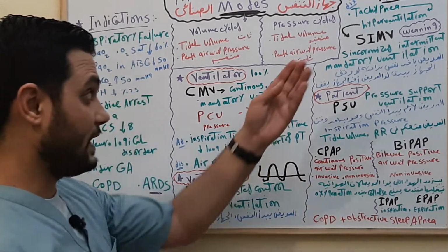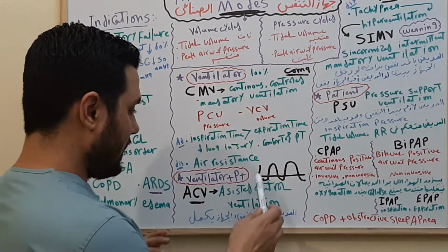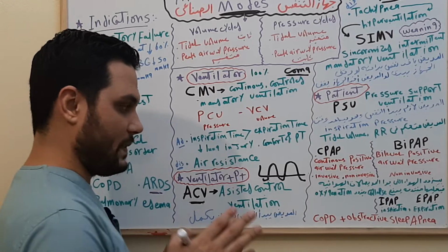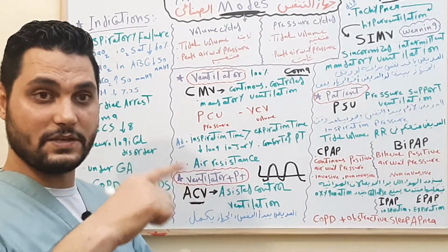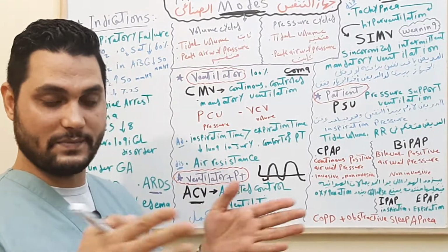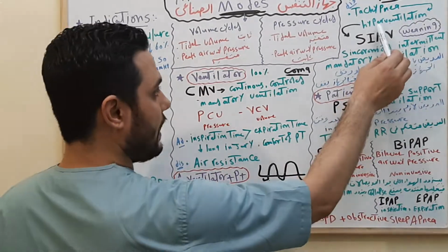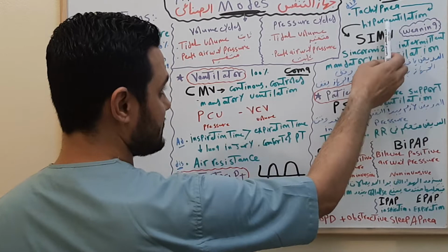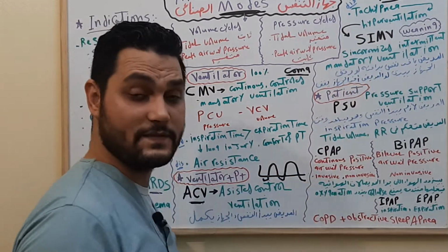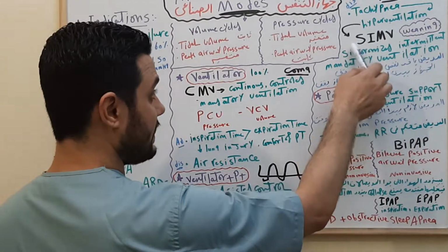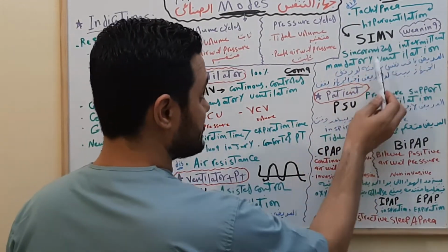If the patient has tachypnea, in this mode the ventilator doesn't understand. When the patient starts ventilation, it continues. So the patient has tachypnea, and the machine will cause hyperventilation. At this time, we need to solve this hyperventilation. So we can sedate the patient to let the patient relax, okay, or transfer to SIMV.